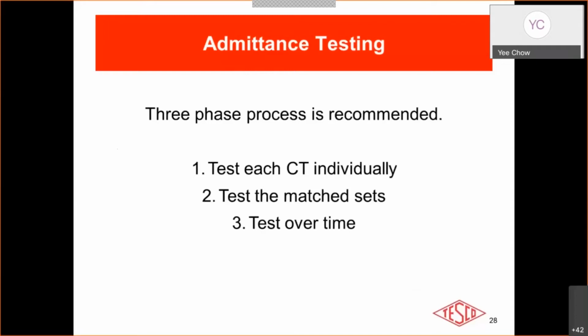However, admittance testing is widely used because it is the only no-load CT test method available. Burden and ratio testing, by their nature, mandate that you have 10% of the rated current for the CT to get a legitimate result.